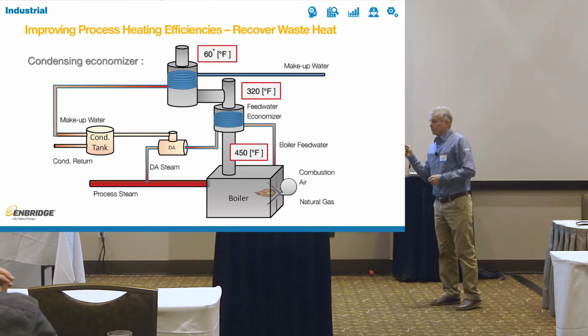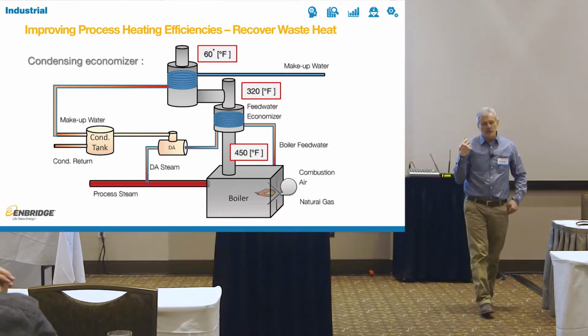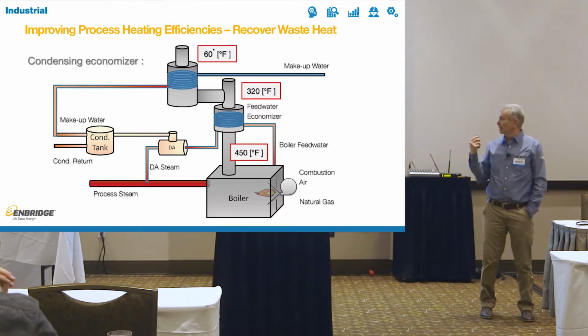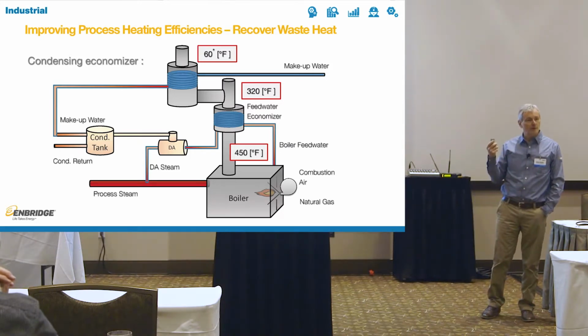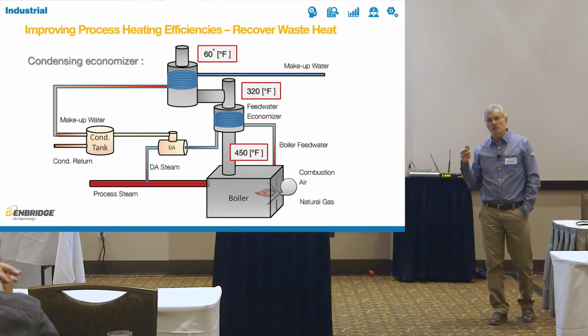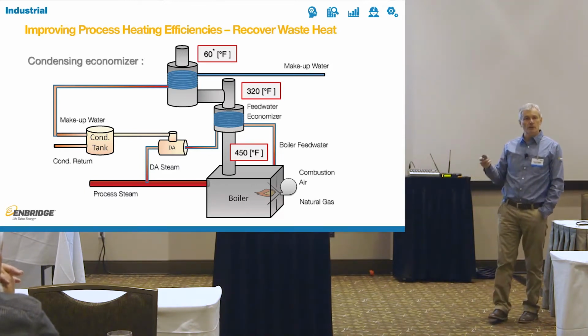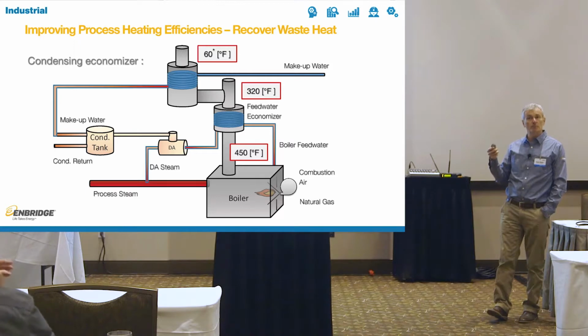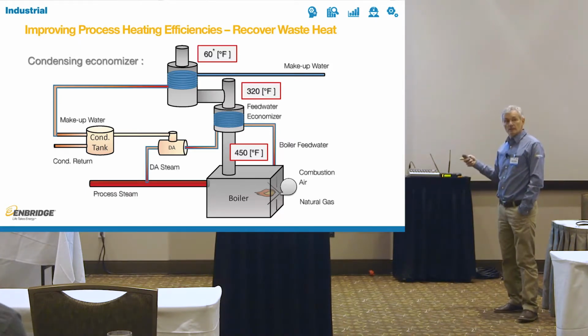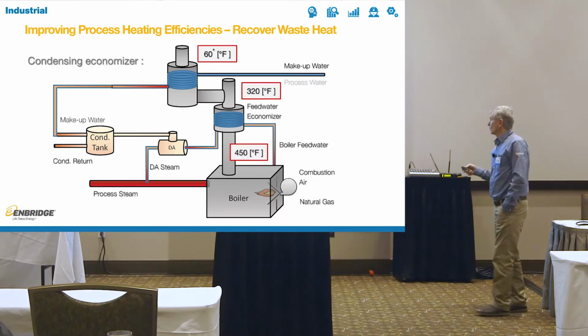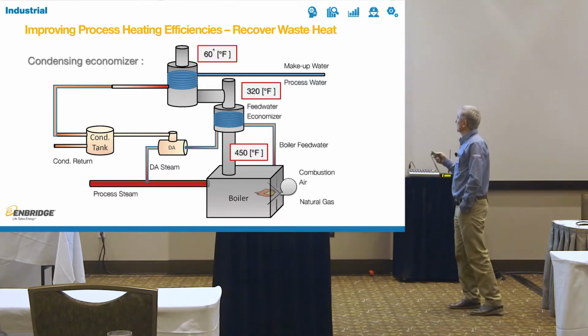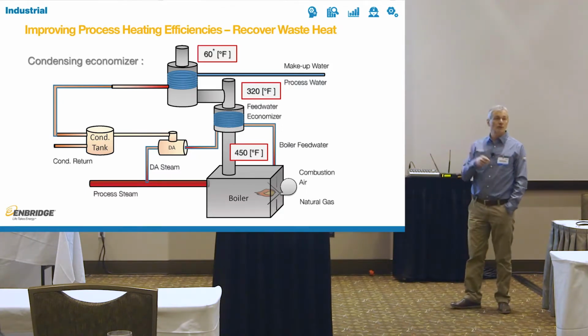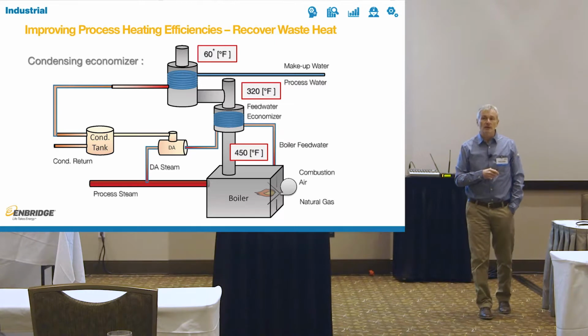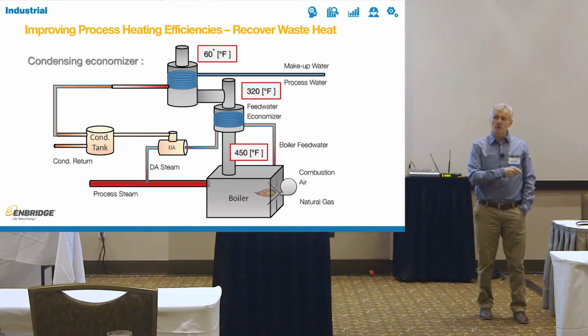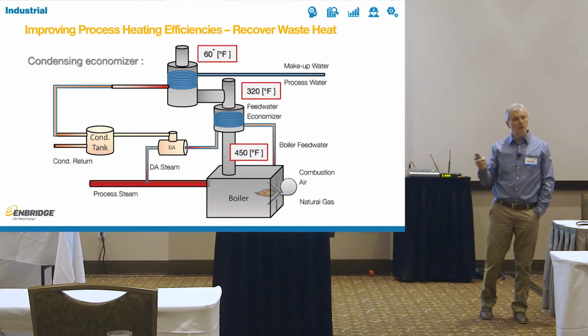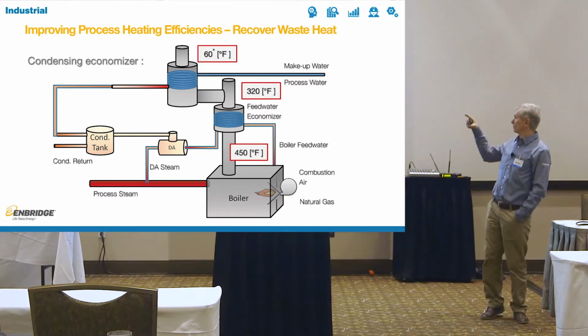But to me, the benefit of condensing economizer is not that. That is a good application for those who only run boilers. But for most of us in the industry, we don't run just boilers. We also need water. We need process water, a lot of process water that we heat in something else. So I like condensing economizer because I can take my process water and put it through the condensing economizer. So it's not tied to my boiler, it's tied to my process. Whenever I need hot water, I put it through the condensing economizer.